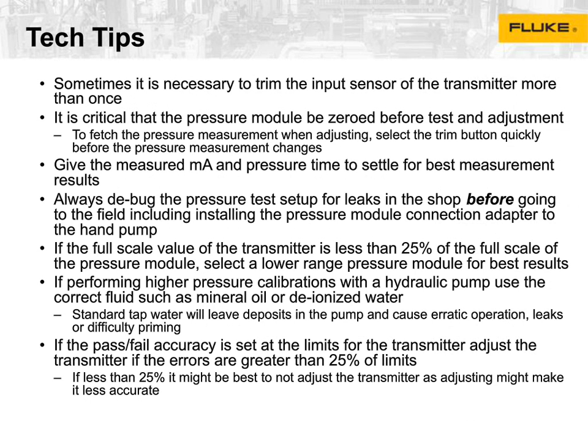Last but not least, we're going to talk about the tech tips. One of the things we find is that a lot of times it's necessary to trim the input sensor more than once. Just depends on how long it's been since the unit's been calibrated and what kind of outputs you get. If you see, like you saw there, where everything is out of tolerance, that may be a good sign that you need to go trim the inputs again. You've got to zero it. If you don't zero the unit, you're going to get strange readings. Things will not work properly. It has to be zeroed.